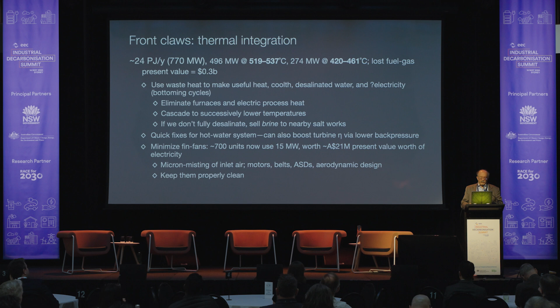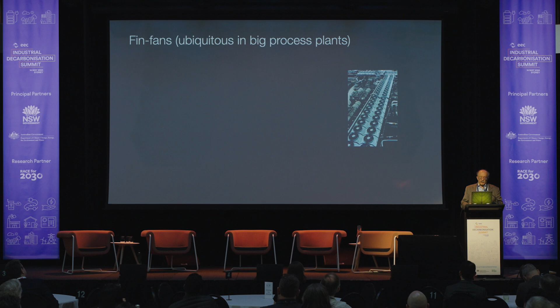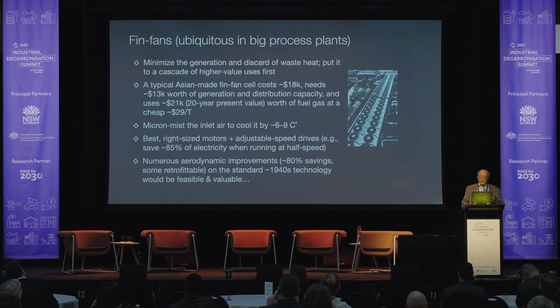And the fin fans could be run much better, but better to redesign them. So after minimizing the heat to be rejected, we would scrap the existing fin fans and put in redesigned ones, micron misted on the inlet, with very efficient motors and adjustable speed drives, and above all with aerodynamics much better than the standard antiques that they had, which were 1940s vintage.